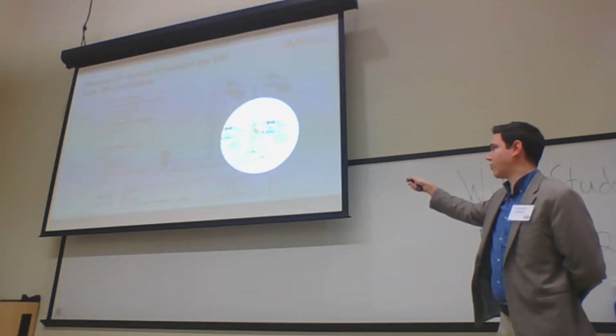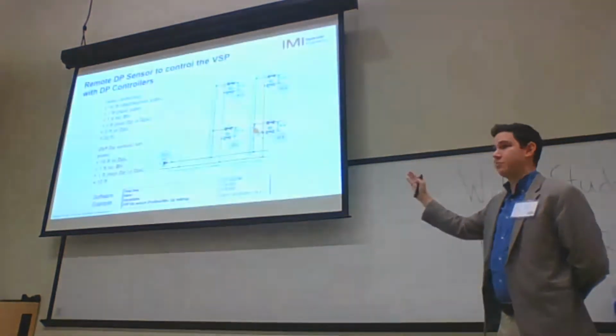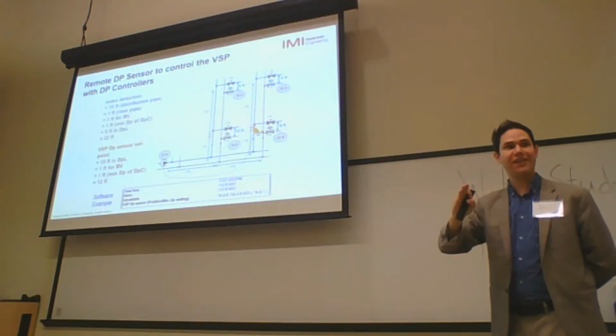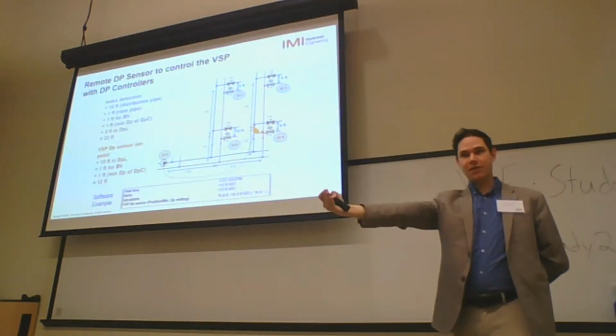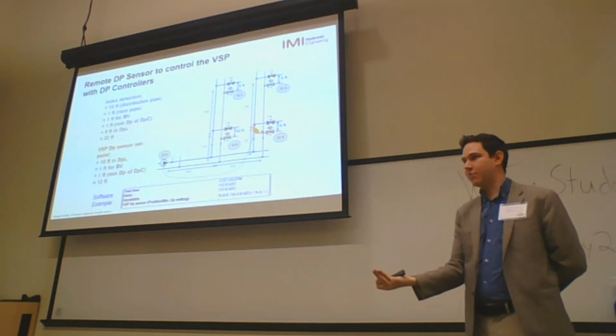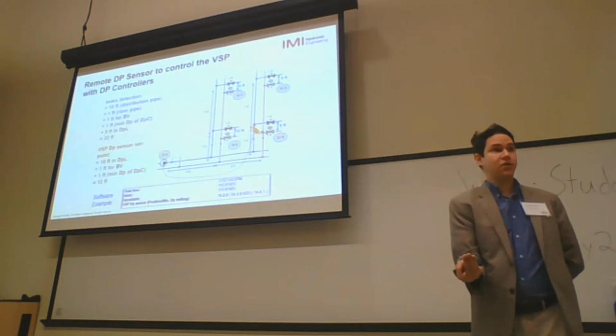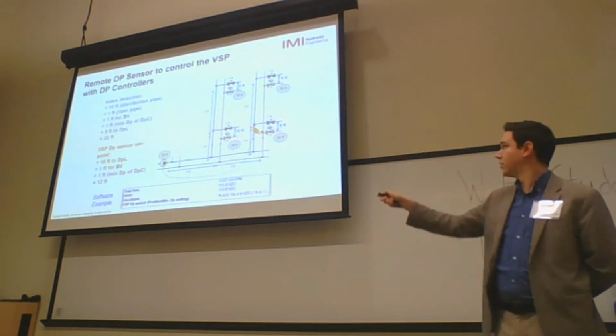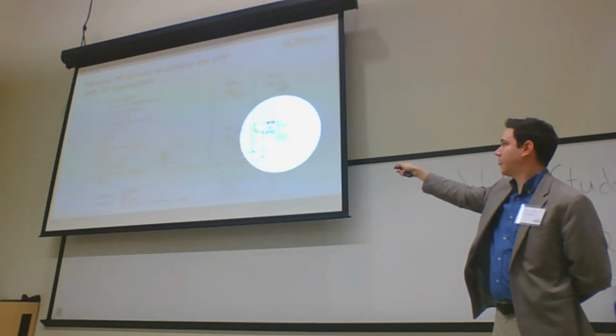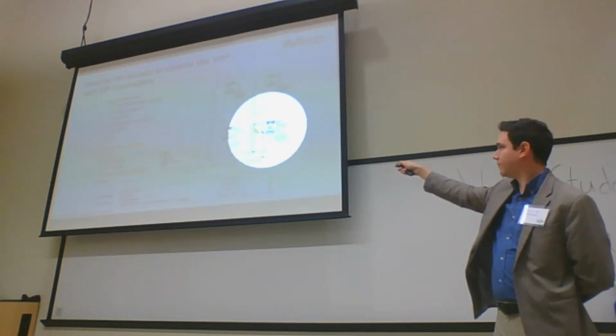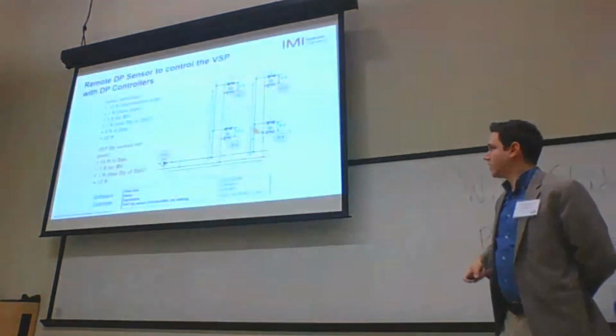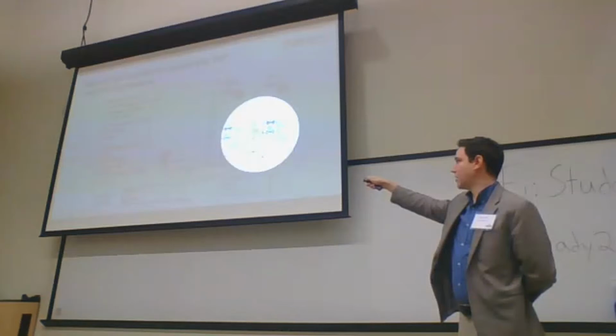Also extremely important, as we saw before: the DP sensor should always be before the DP controller. Because if you place it downstream, the DP controller would always be measuring the same number. It should not be done that way. It should always be before, like you have in this case. The DP sensor is the yellow thing right there, and the DP controller is right there. Never put the DP sensor inside the branch. So I found my DP sensor location by finding my index branch.